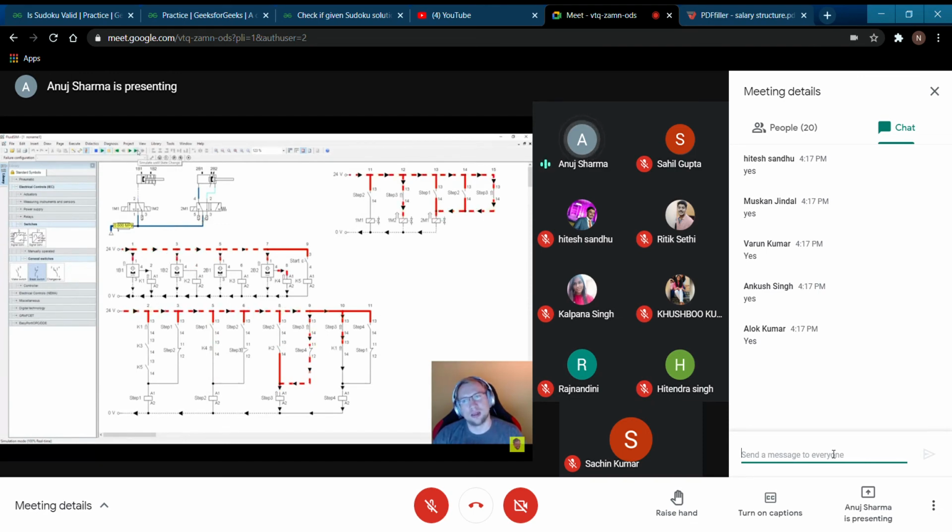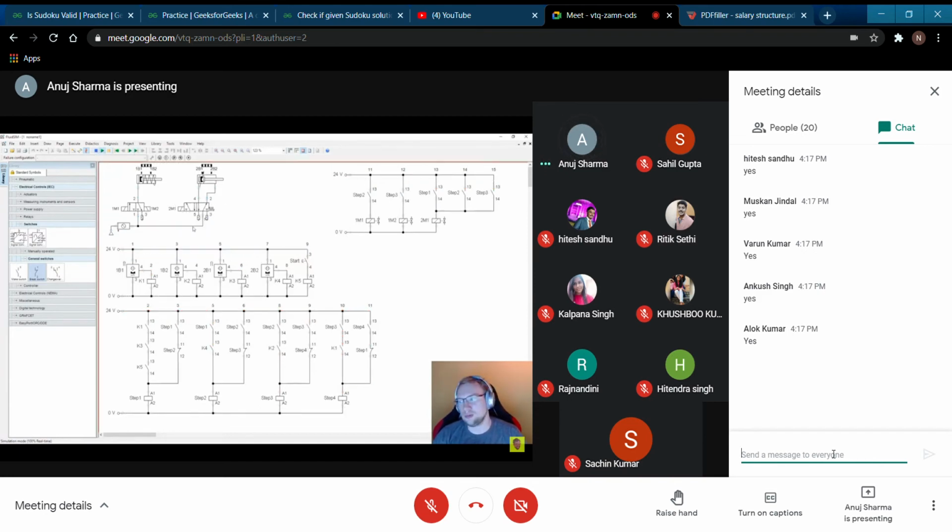And as soon as we reach 1B1 here, K1 will close, step 4 will activate, step 4 is active. We'll deactivate step 3, right? Step 3, only step 4. Everything here is deactivated. This has a return spring and will return back. There we go. Good. That's good. That's pretty much what I want, right? That's pretty much what I want.